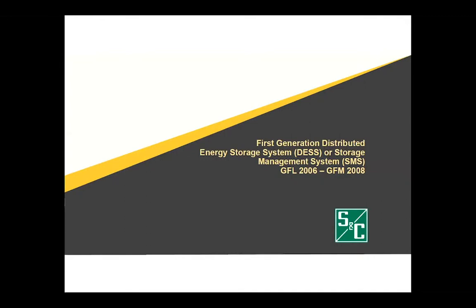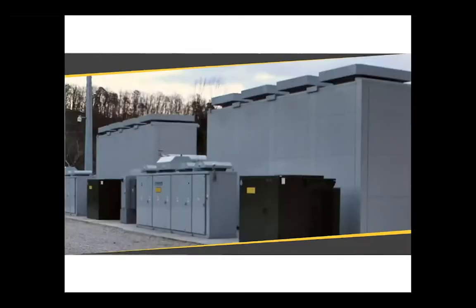So as time progressed, we started our next inverter development, which was a system that worked with a fairly large battery. I've got a picture of one of our early systems that was using grid forming. You can see 2 transformers are the green boxes. Those are 1.5 MVA transformers, 2 inverters between the green boxes and off to the edge of the picture. And then behind those was the battery. This is a sodium sulfur battery. Each box was 1 megawatt, 6 megawatt hours. So this is a 12 megawatt hour system.